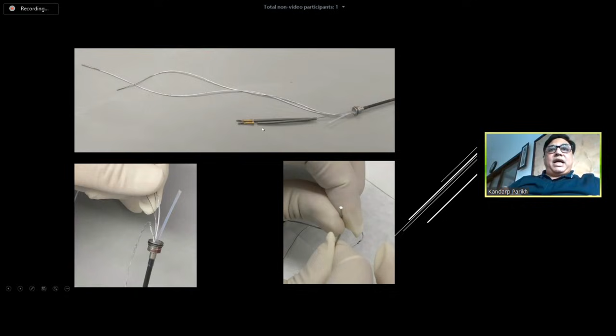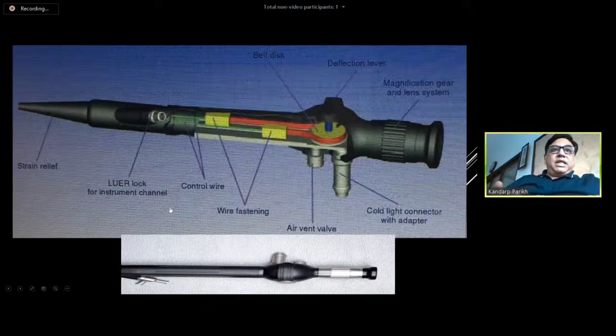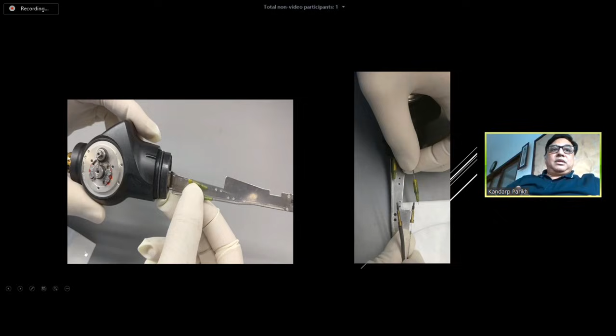Now this is the handle of the scope. So if you open the scope handle, what you see inside are these 2 wires with the adapters, which will fit into the adapters coming from the shaft here. So this is the wire fastening. These are the 2 wires with the adapters coming from the shaft, and these are the 2 wires coming from the handle with the adapters, and then they can snugly fit into each other. If you look here, you can see these wires move over this pulley. So when you press the deflection lever, there is a movement of this wire, and that will produce the deflection.